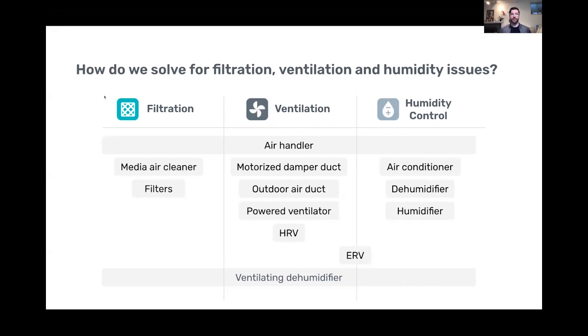But there's actually filters in everything. There's typically filters in your ERV, HRV. There's filters in your humidifier, dehumidifier, and there can be filters on your outdoor air duct. So it's amazing all the places that you find filters now. Ventilation, what we see, and first of all, the air handler goes across all of this because you don't get any of these without moving the air. You cannot filter particulates out without moving air through the filter.